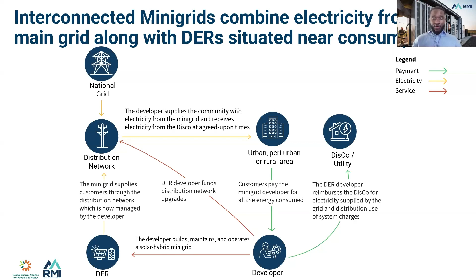This is a visual representation of a simple interconnected mini-grid architecture. The IMG in this example is receiving power through a 33 kV feeder from the grid. That 33 kV power is stepped down to 415 volts and blended with the power coming from the interconnected mini-grid generation plant. So the solar PV, the battery system, the diesel genset, and the grid all feed into a distribution panel with protection equipment before being stepped up and fed back into the community.